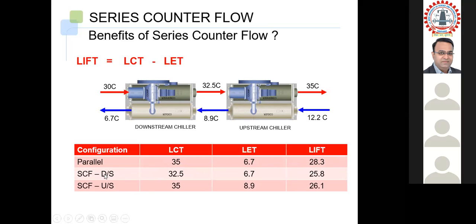But if you put two chillers in series counterflow, the downstream chiller has a lift of 25.8 and the upstream chiller has a lift of 26.1. The upstream chiller is the one which receives the chilled water at 12.2 degrees centigrade, and the downstream is the one which produces a chilled water temperature at 6.7 degrees centigrade. So this is how upstream and downstream chillers are counted.